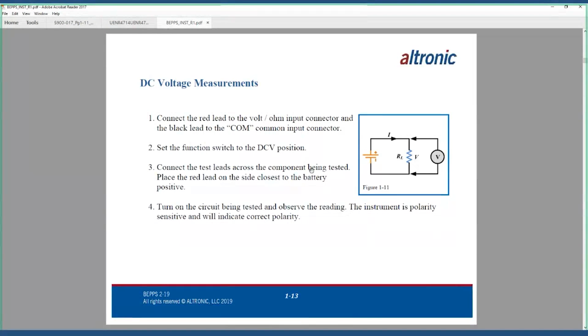The instrument is polarity sensitive and will indicate polarity too. So again, if I hook the red probe of the meter to this side, the positive side source, and I put the black here, what I should see is just voltage. If I reverse and push the black on this side and the red on this side, I should see a negative sign in front of my value, indicating that I have reverse polarity on my test. Now, if all I'm doing is looking for voltage, it doesn't really matter. But if I'm on an unknown circuit and I want to know where my positive source is coming from, where my negative source is coming from, that's a useful, handy fact and a tool built into our meters.